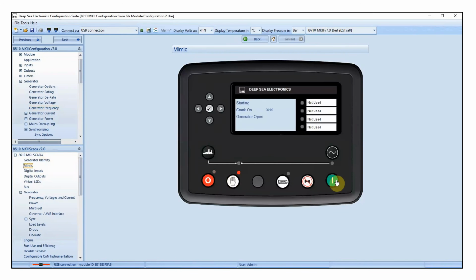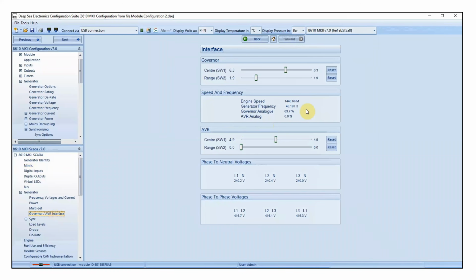So here I am starting the generator. And remember, you can only request the DSE module to close the generator breaker when the LED underneath the generator button turns on, like so. Generator is now on load. And if we go to the governor and AVR section, you'll see the frequency has started to come down. And eventually, when it gets to 47.5 Hertz, that governor analog percentage should be somewhere between 75 and 85%. As we can see in this example, it's about 84%, perfectly fine. So all I'll need to do now is go back to the Mimic page, tell the genset breaker to open, and stop the generator.